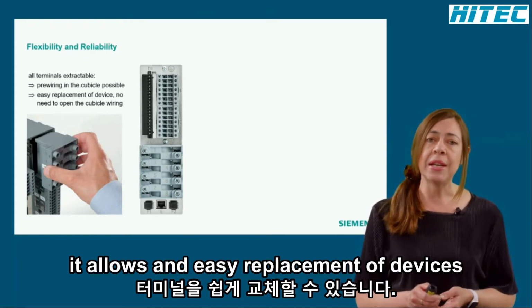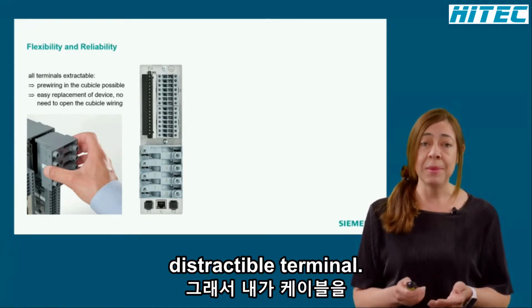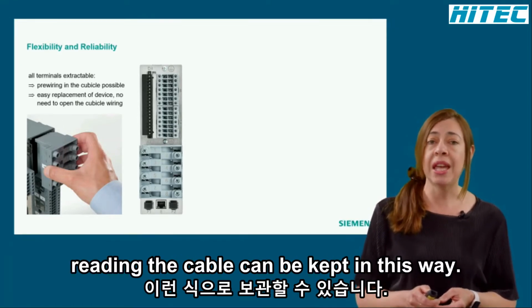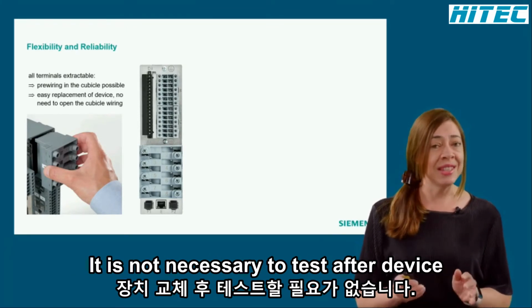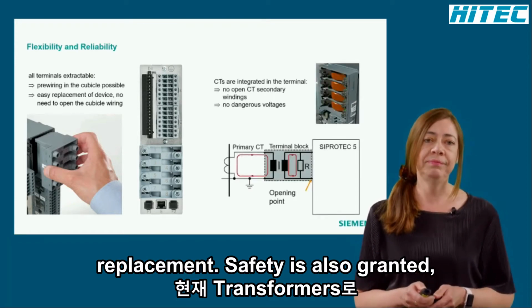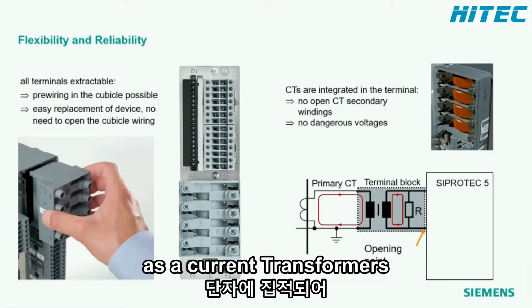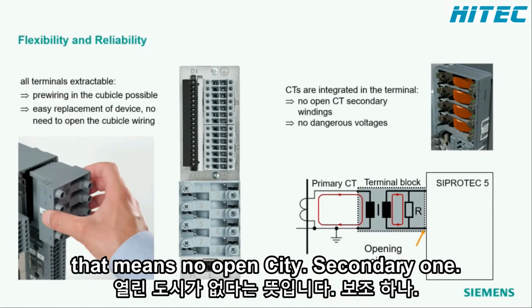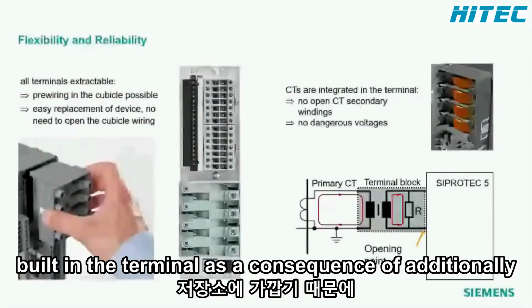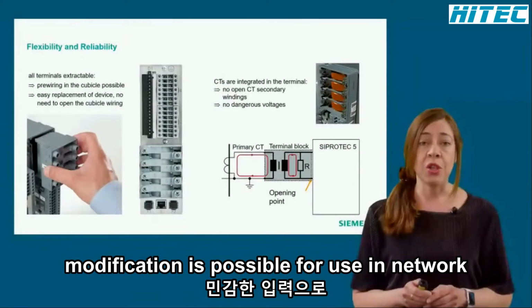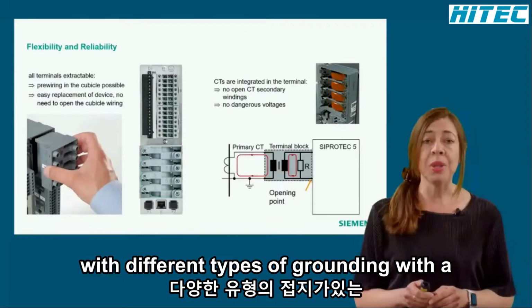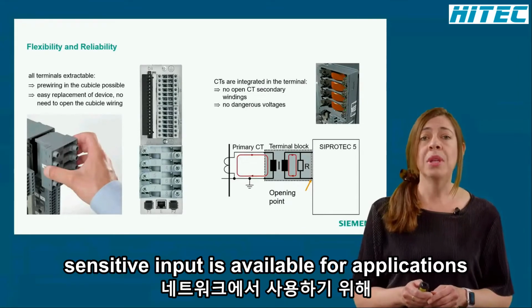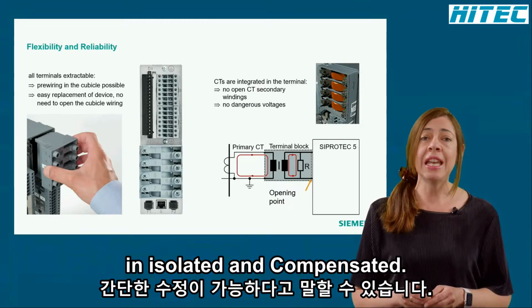Second, it allows an easy replacement of devices. Unplug the extractable terminal from the device so the wiring within the cubicle can be kept. In this way, it is not necessary to test wiring after device replacement. Safety is also granted as the current transformers are integrated in the terminal. That means no open CT secondary windings. The current loop of the primary CT is always closed by the resistor built into the terminal. As a consequence, there is no generation of dangerous voltages. Additionally, we can say simple modification is possible for use in networks with different types of grounding. A CT block with a sensitive input is available for applications in isolated and compensated networks.